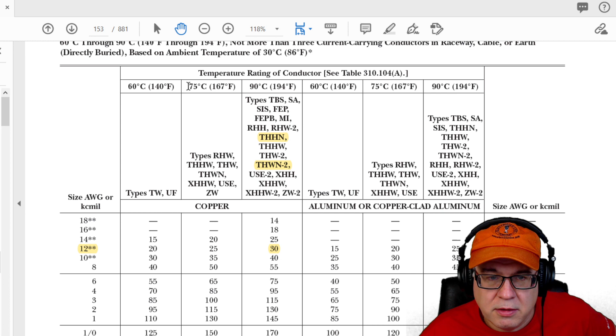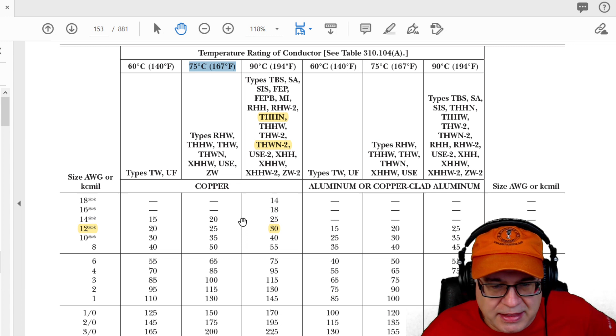Now we're under the 75 degree column, and no other conditions of use were applied - no heat, no bundling, nothing mentioned, so I don't have to think about that. I'm looking for something good for 110 amps. Looks like a 2 AWG is good for 115. Looks good to me. So going back to my question, I'm going with a 2.